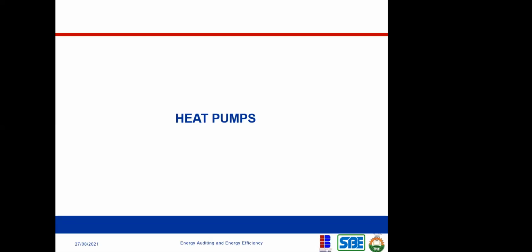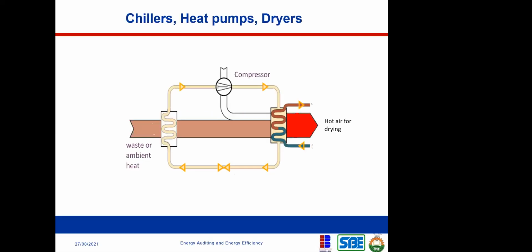So let us talk about heat pump. Now, heat pump is similar to your air conditioning system, but opposite. Your air conditioning system absorbs heat from your space and dumps it into the environment, right? But what your heat pump does is this: it collects the heat from your environment, it compresses it, and it becomes hotter. Then you pass a fluid, maybe water, to collect that heat, and you're dumping that heat into your water. So you can use a heat pump to generate hot water from the air. We call it air to water heat pump.